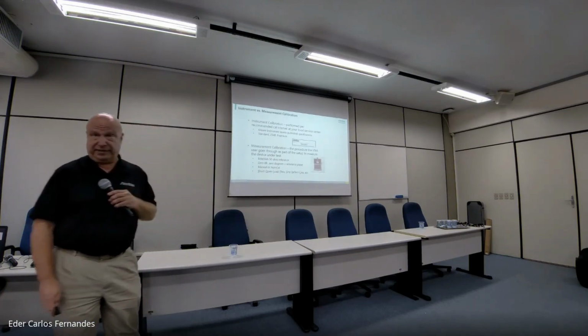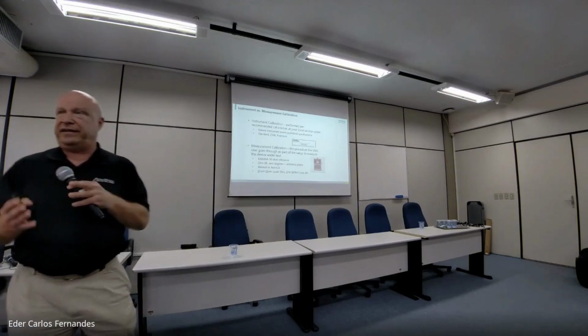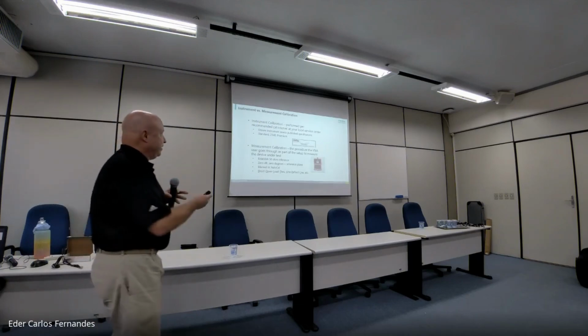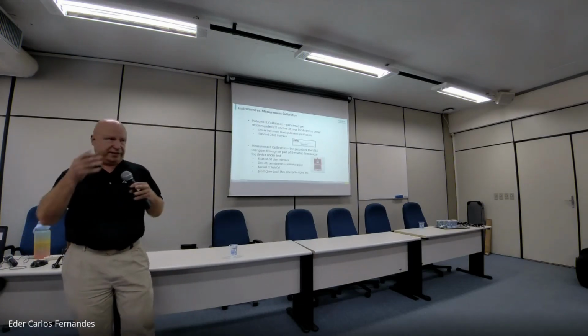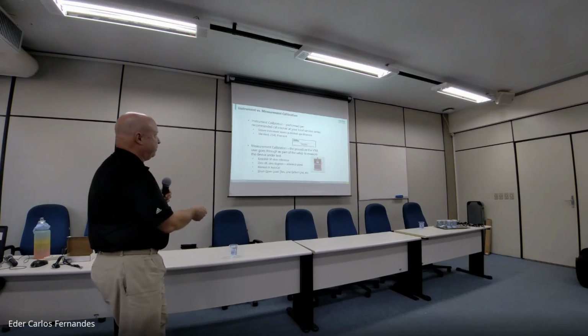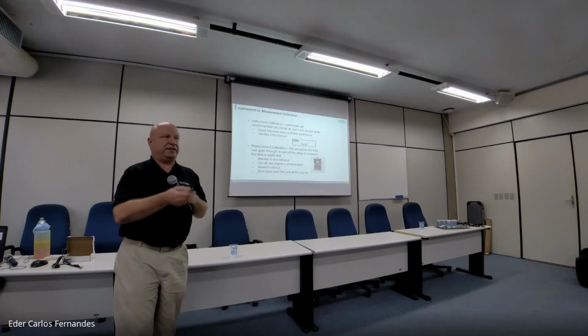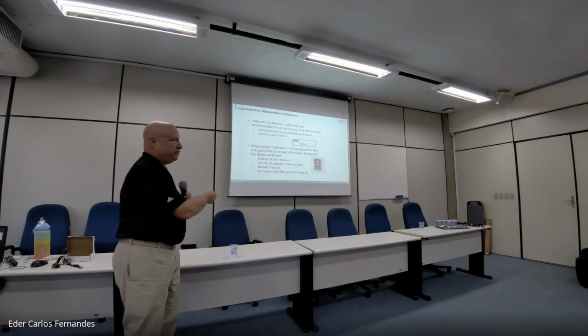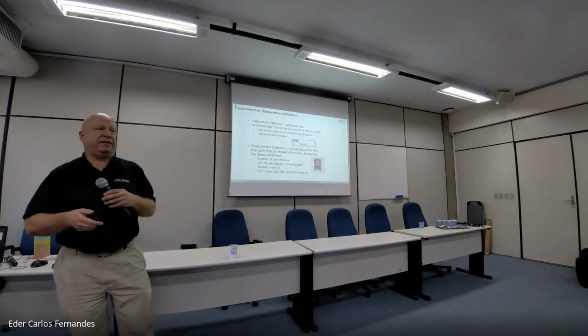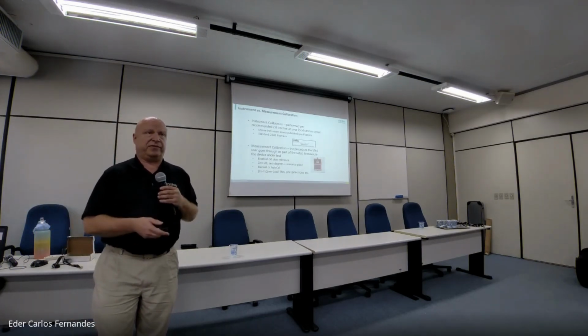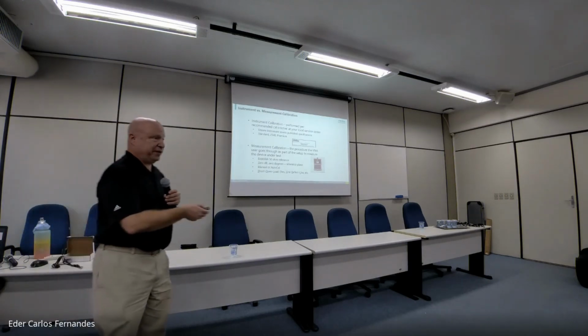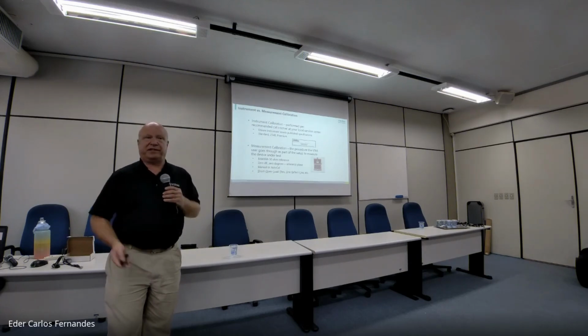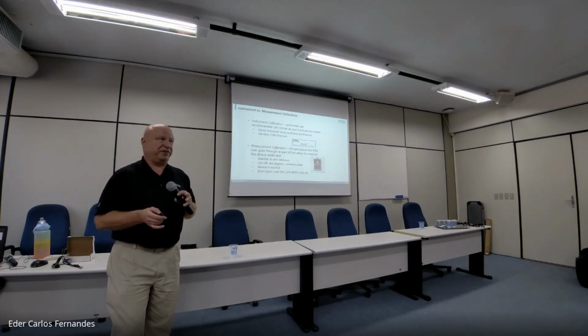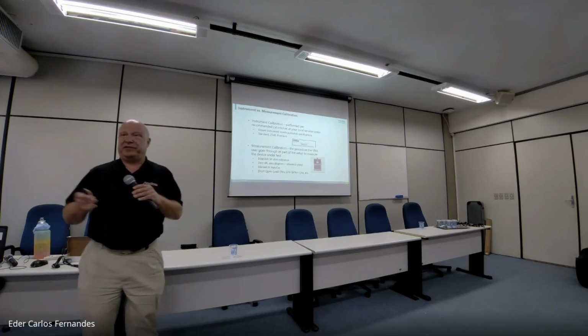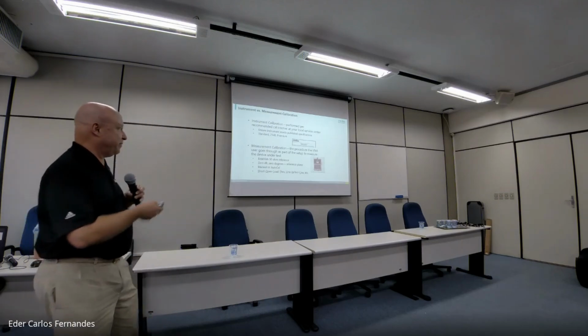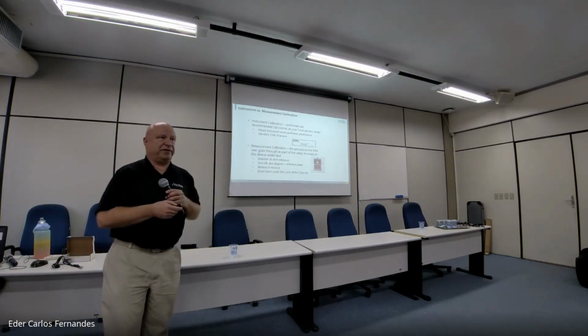Now, calibration. This is a topic that is a little bit different for the VNA versus the spectrum analyzer or the power meter. Every instrument gets sent to a cal lab to be calibrated, and you get the sticker and you get the calibration certificate for that. But in the case of the VNA, it's a step further. We'll get that calibration done for power and frequency, but beyond that, it's really up to the user to do the calibration that's required to make an accurate measurement. Because without the measurement calibration that the user does, you can't get a good result at all. And every user is a little bit different. No two users I've ever met for VNAs are exactly alike. So the amount of care and technique that each one provides to this kind of process is very important to the result of the measurement.